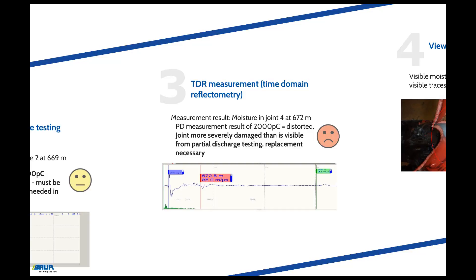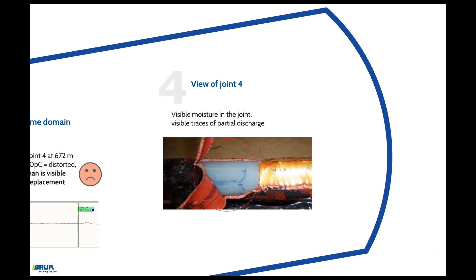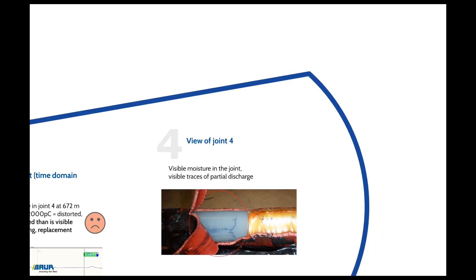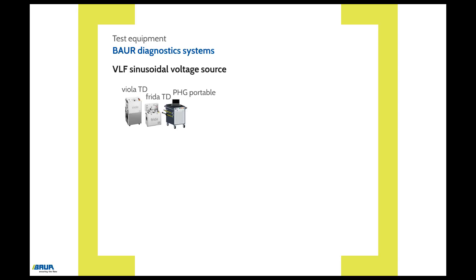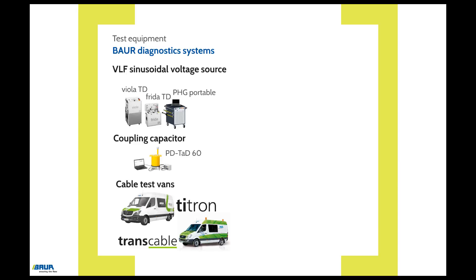The partial discharge measurement of 2000 pC is therefore a distorted result caused by the moisture in the joint. The joint is more severely damaged than can be seen from the partial discharge testing and should be replaced immediately to prevent a failure during operation. The subsequently exposed joint exhibits clear traces of partial discharges as well as moisture. The decision to replace the joint immediately was therefore appropriate. To perform measurements like the one described in the example, a VLF sinusoidal voltage source is required, such as FridaTD, ViolaTD, or PHG from BAUR. With the PD-TaD 60 partial discharge diagnostic system and a PC to control it, the measurement of the dissipation factor and partial discharges can be performed in parallel. This is also used as a system in the cable test vans.